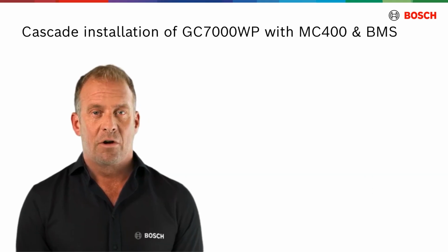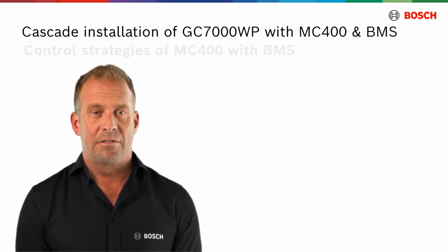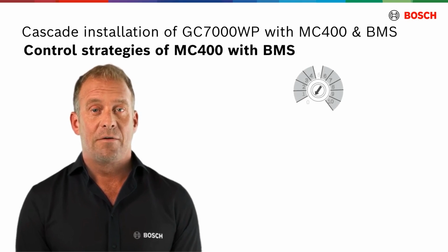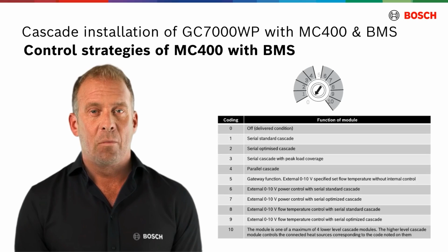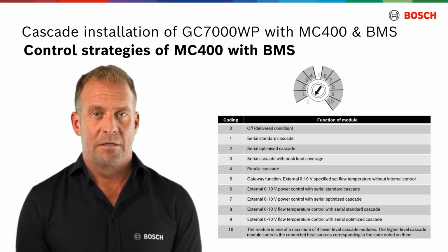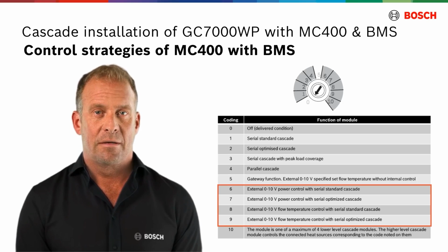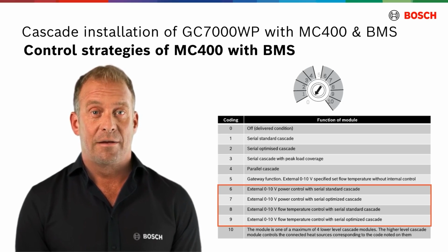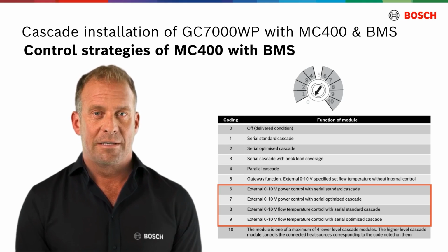The MC400 module enables users to select a control strategy through the position of the address coding switch. When the boiler cascade is operated by a 0 to 10 volt request from the BMS, 4 cascade control strategies can be set, corresponding to address code switch positions 6, 7, 8, and 9. We will examine these strategies in detail.